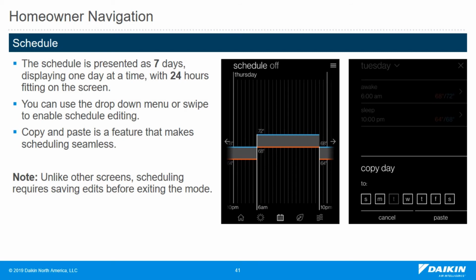The calendar is for scheduling, and you'll see in the center of the screen there the very visual. This is where my schedule's set. When you touch that screen, it will go to the screen shown on the right, which lists the days individually and shows you your awake time, your sleep time, your leave times, and allows you to change the temperature of each one of those times. You can copy that day to the next. So if you did a Monday through Saturday, you can program Monday once, copy them all the way through Saturday, and then you can do Sunday on its own.